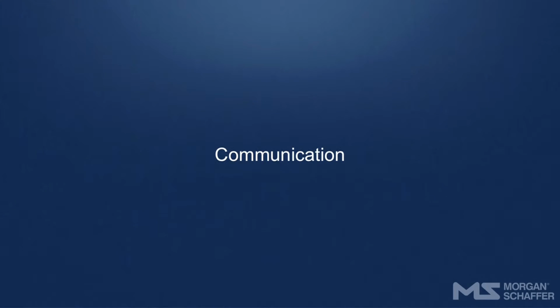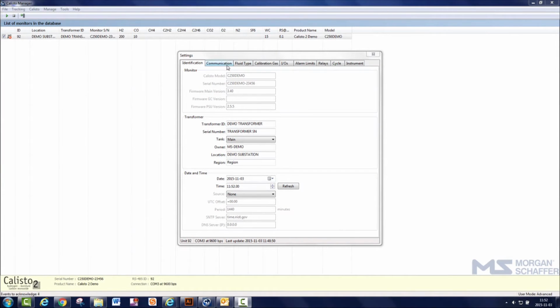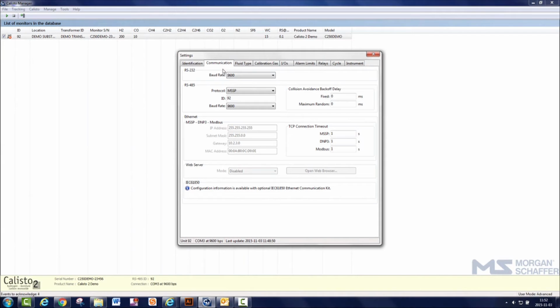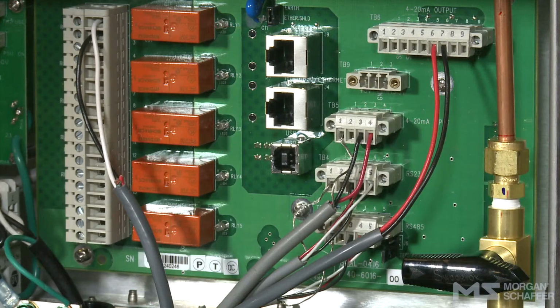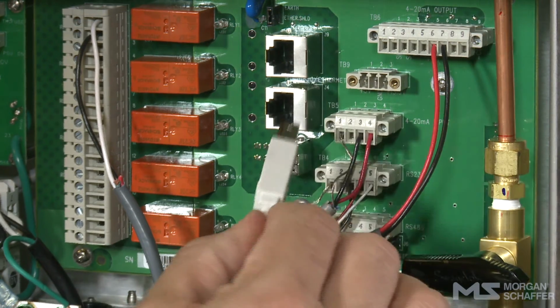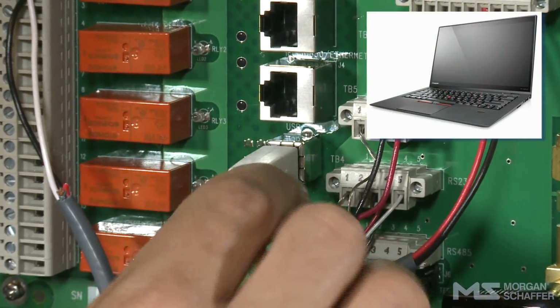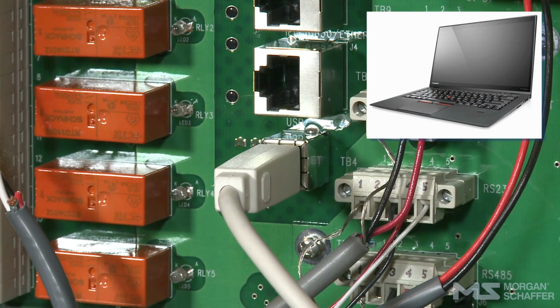Communication. Calisto monitors offer native support of 3 communication protocols: Morgan Schaffer systems, Modbus, and DNP3 Level 2. The preferred method of adjusting the communication settings is through a local connection between a laptop PC and the Calisto USB port.